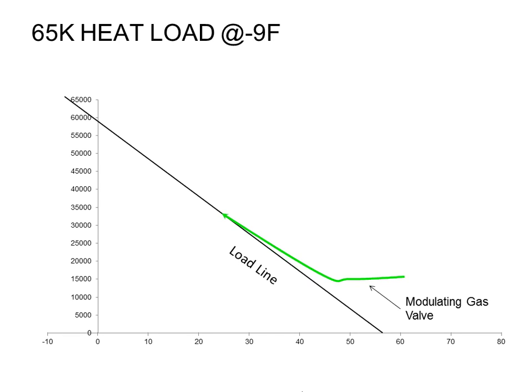it's not a good idea for them. And the reason being is that you want the modulating gas valve to always stay open, to always be flowing heat, to always provide BTUs to your house, because then you're going to have a consistent discharge air temperature.